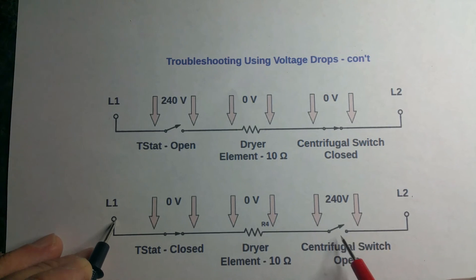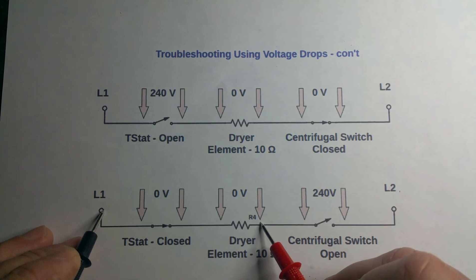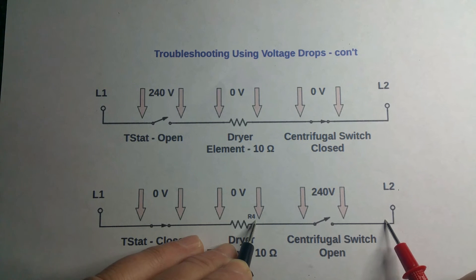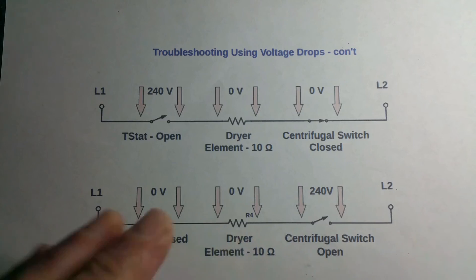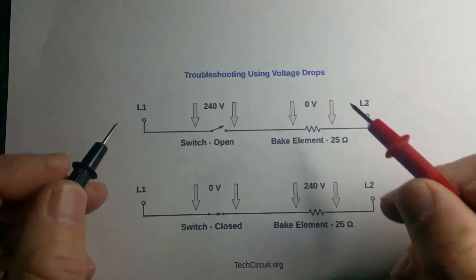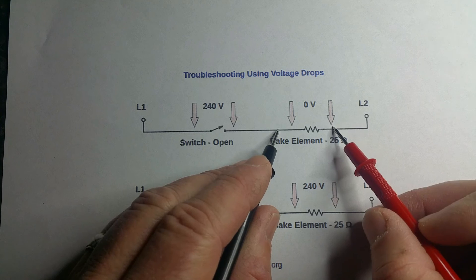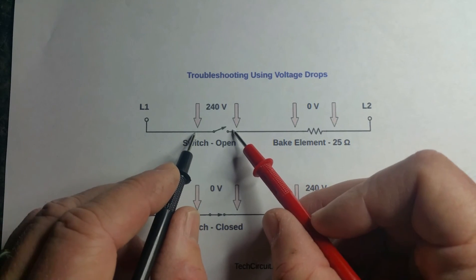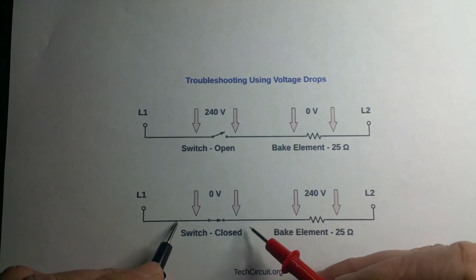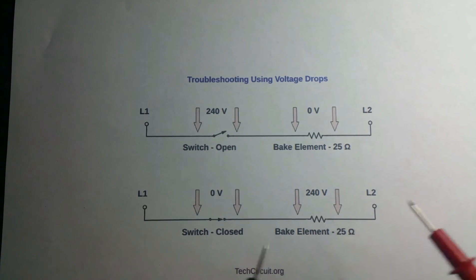Actually, if the thermostat is closed you get zero volts there, but if the centrifugal switch is closed, you're going to get 240 volts from here to here because the thermostat is closed. And if you check from here to here and the centrifugal switch is open or bad, you're going to get 240 volts; when it's closed you get zero volts. When you check here you get 240 volts and here you get zero volts, because all your voltage is appearing across the open switch with infinite resistance. That goes back to the rule — zero volts across a closed wire, because of Ohm's law.